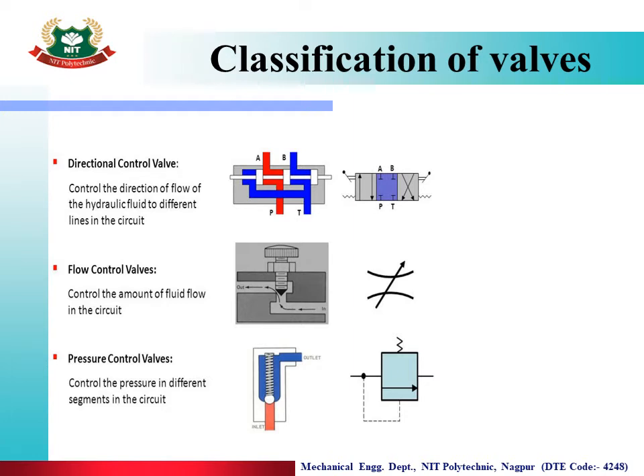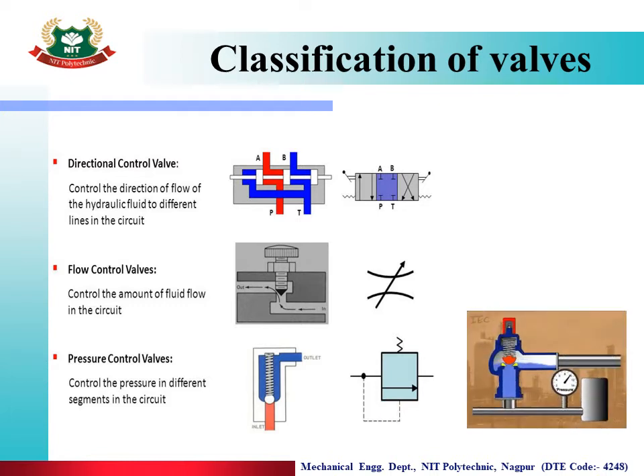Pressure Control Valves control the pressure of fluid in the circuit, whereas directional control valves control direction and flow control valves control flow rate. The pressure control valve adjusts pressure with the help of a spring. When pressure is low, the valve remains closed; when system pressure rises, the valve opens and stops when pressure reduces.